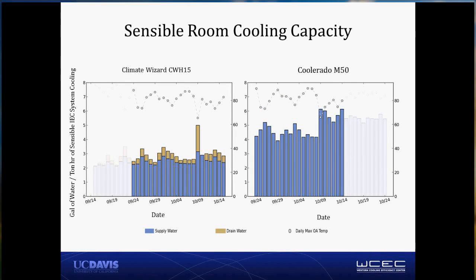Now, it's important to normalize those numbers by the total amount of cooling that's being delivered by the system, and put it in terms of gallons consumed per ton-hour of sensible system cooling. For the Climate Wizard, we're looking at between 2 and 3 gallons per ton-hour consistently over the entire period of evaluation. The Coolerado is marking out more like between 4 and 5, some days up to 6. So these numbers are consistent with the targets put forward by the Western Cooling Challenge for gallons of water consumed per sensible ton-hour.